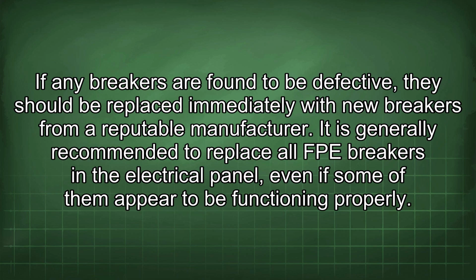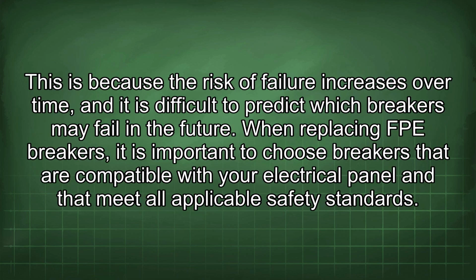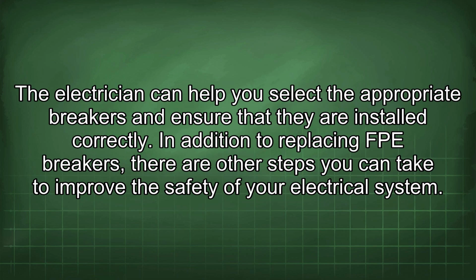It is generally recommended to replace all FPE breakers in the electrical panel, even if some of them appear to be functioning properly. This is because the risk of failure increases over time, and it is difficult to predict which breakers may fail in the future. When replacing FPE breakers, it is important to choose breakers that are compatible with your electrical panel and that meet all applicable safety standards. The electrician can help you select the appropriate breakers and ensure that they are installed correctly.